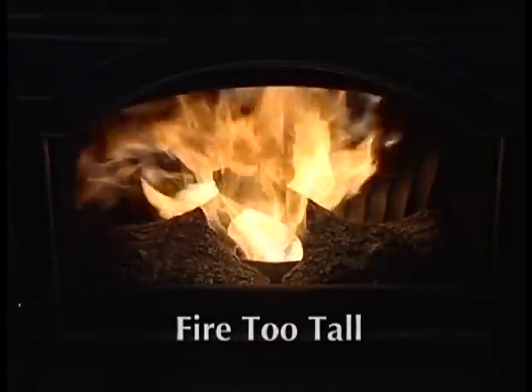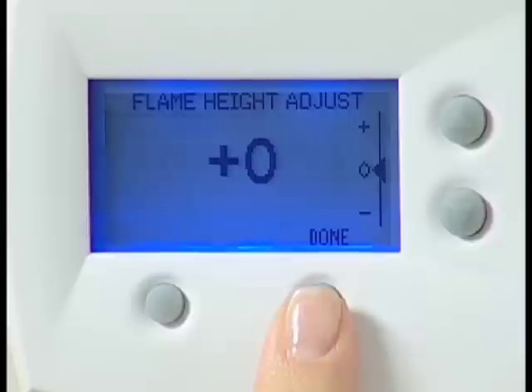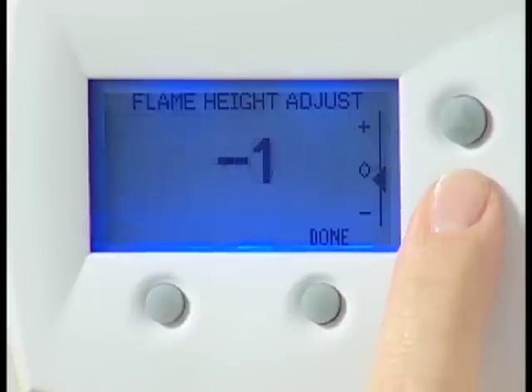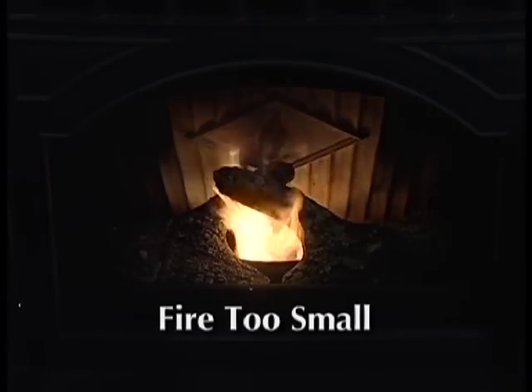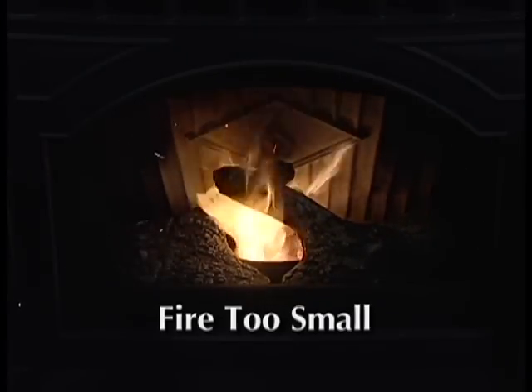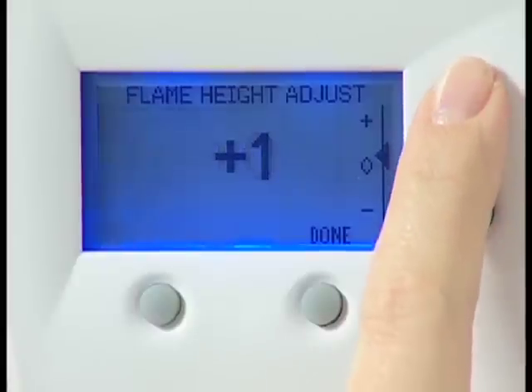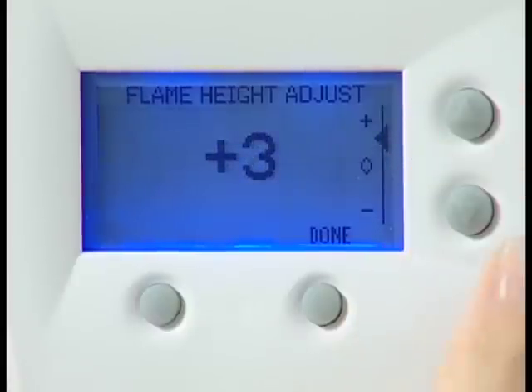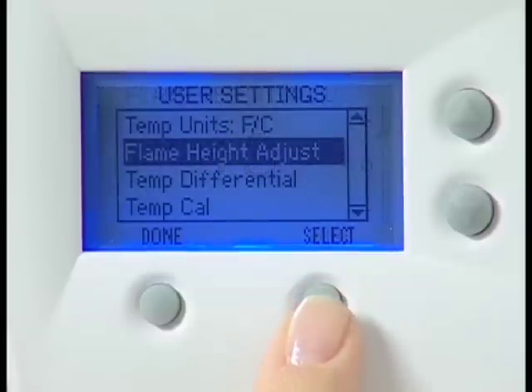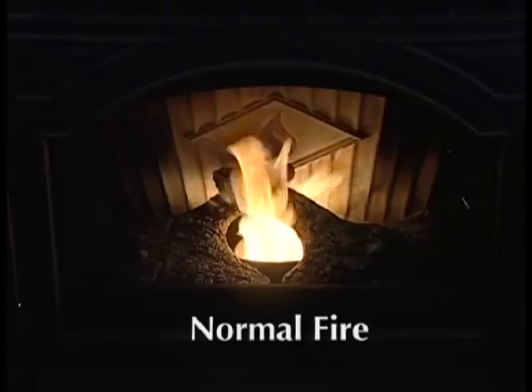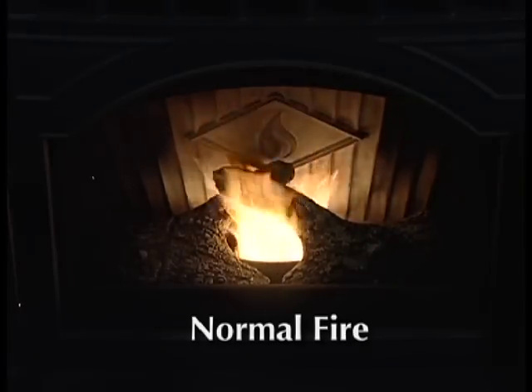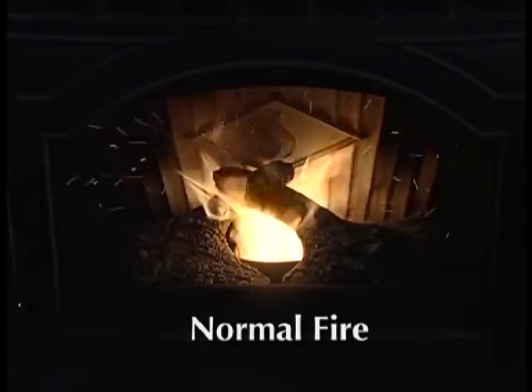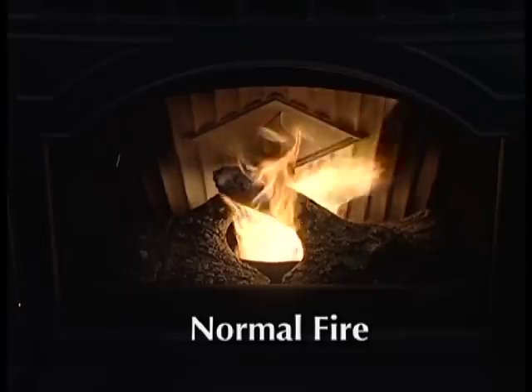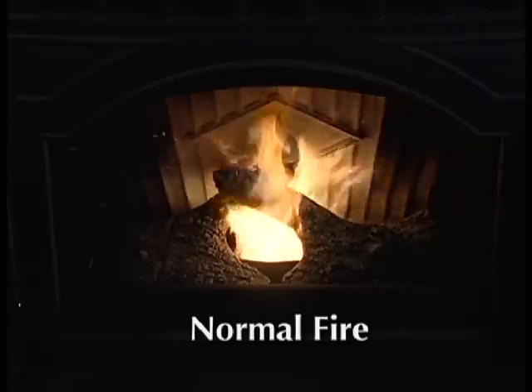If the fire is very large, but lazy with black smoky tips, reduce the flame height. On the other hand, if the flame is small and very active, increase the adjustment. Allow 10 to 15 minutes after each adjustment for it to take full effect. A properly adjusted fire with the heat output on high has an active flame pattern that exceeds 8 inches. This is normal on a Quadra-Fire Advanced Energy unit.